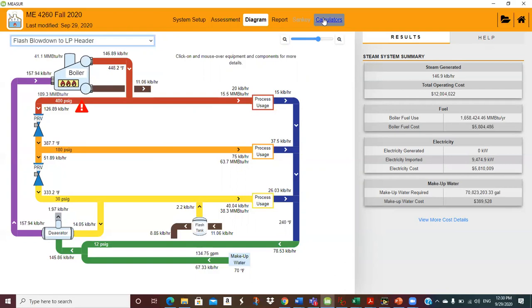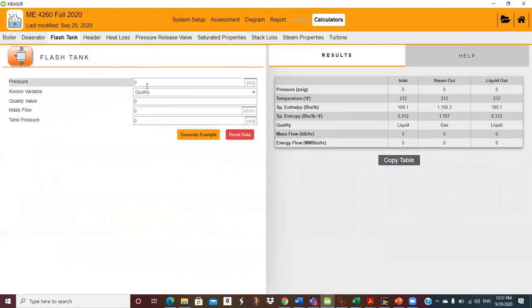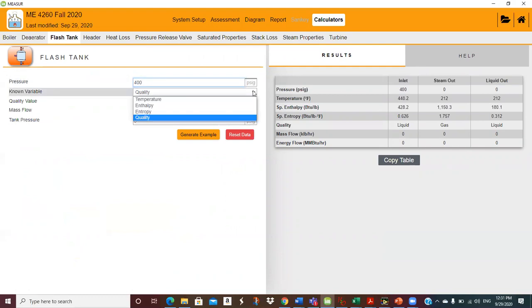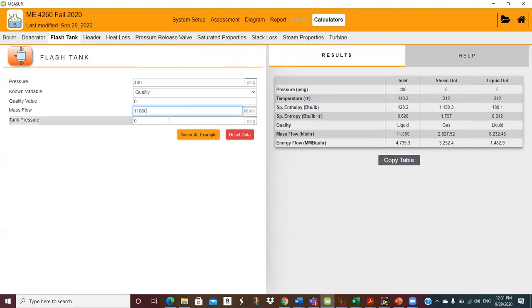2,200 pounds an hour — that's a fair amount of steam. Using the flash tank calculator: pressure 400, quality zero (saturated liquid), mass flow 11,060, tank pressure 30. Steam out: mass flow 2,203.55 pounds per hour. When it shows in the model it rounds to one decimal point. That's 2,200 pounds an hour — that's the process going on.